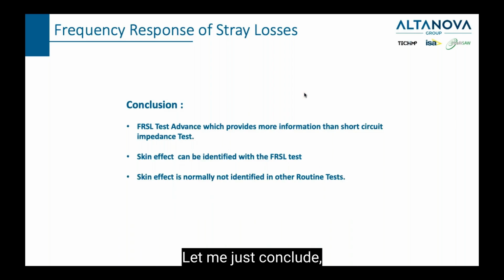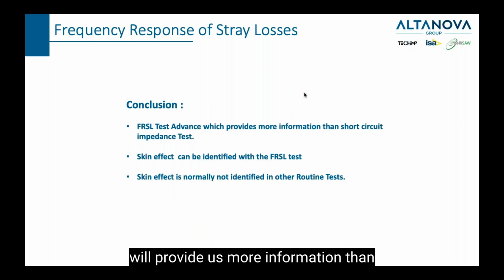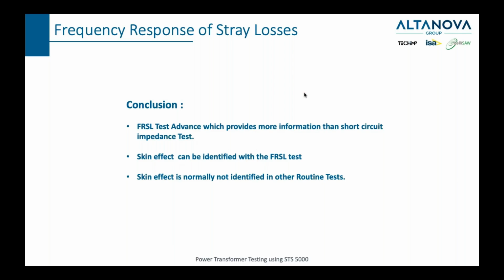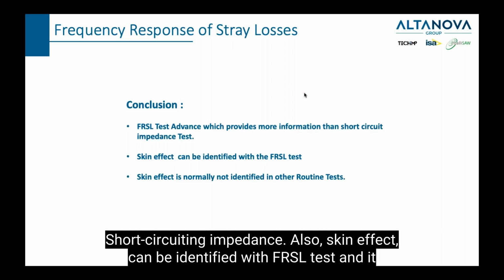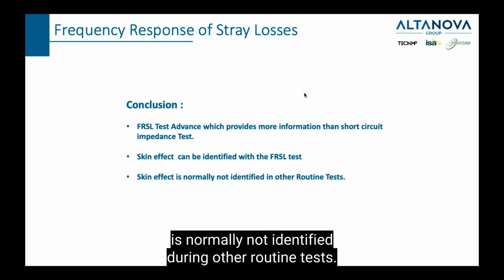Let me just conclude. Frequency response of stray losses will provide us more information than short circuit impedance. Also, skin effect can be identified with the FRSL test, and it is normally not identified during other routine tests.